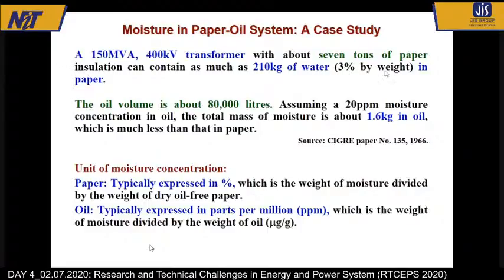Now, if I say that it has 3% by weight of moisture, so 7,000 kilogram of paper, 3% present in paper. Just try to imagine this. 210 kilogram of water is present. That same transformer has oil of 80,000 liters. So my dear participants, try to understand that we are talking about really, really big things. And if I say that 20 parts per million is the moisture content, which is quite high, and if you convert it into kilogram, it comes to 1.6 kilogram of moisture in oil.